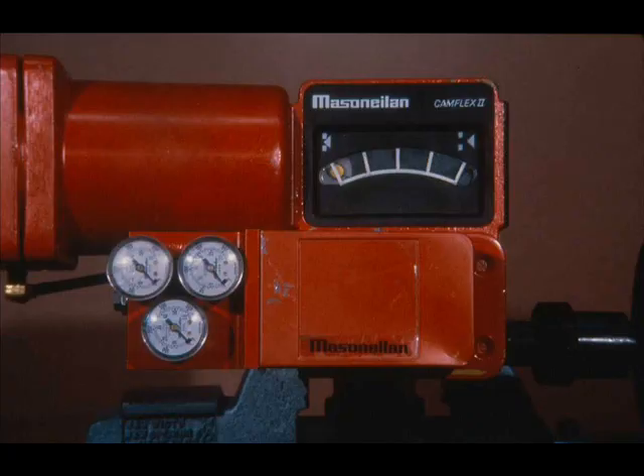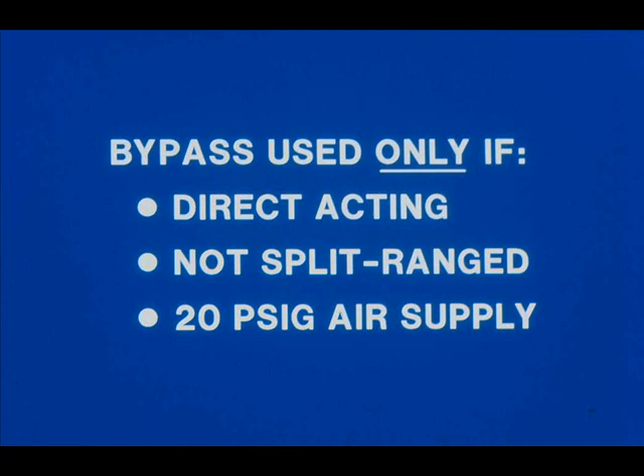When a CAMFLEX valve uses a supply pressure higher than 20 PSIG to overcome the high pressure drop across the valve, the 3 to 15 PSIG instrument signal may not be sufficient to operate the valve when the positioner is bypassed. Furthermore, if the positioner with a high supply pressure is bypassed suddenly, the high pressure in the actuator may damage the diaphragm in the positioner or the control instrument. The bypass valve should be used only if the positioner is direct acting, not split-ranged, and the supply pressure is 20 PSIG.